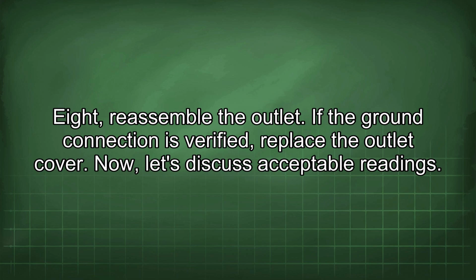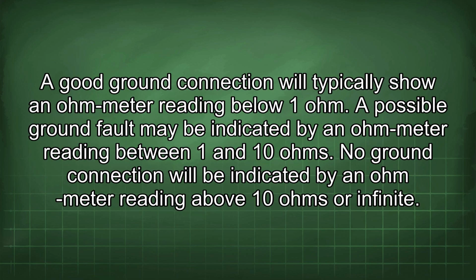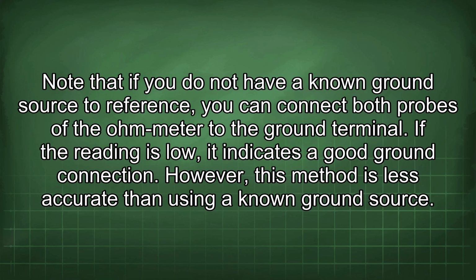Now let's discuss acceptable readings. A good ground connection will typically show an Ohm-Meter reading below 1 ohm. A possible ground fault may be indicated by an Ohm-Meter reading between 1 and 10 ohms. No ground connection will be indicated by an Ohm-Meter reading above 10 ohms or infinite. Note that if you do not have a known ground source to reference, you can connect both probes of the Ohm-Meter to the ground terminal. If the reading is low, it indicates a good ground connection. However, this method is less accurate than using a known ground source.